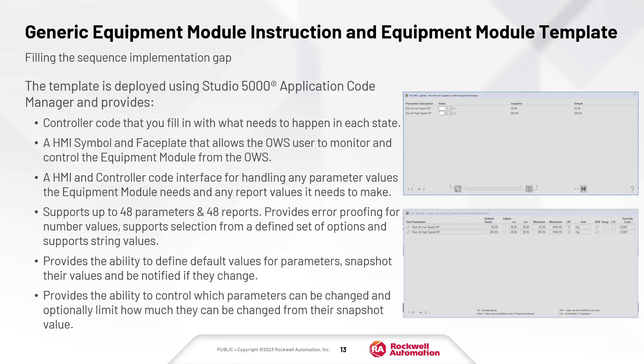The template is deployed using Studio 5000 Application Code Manager and provides controller code that you fill in with what needs to happen in each state, an HMI symbol and faceplate that allows the operator workstation user to monitor and control the equipment module, and an HMI and controller code interface for handling parameter values and report values. It supports up to 48 parameters and 48 reports, provides error-proofing for number values, supports selection of defined option sets and string values, allows defining default values, snapshot values, change notifications, and the ability to control which parameters can be changed and limit how much they can deviate from their snapshot value.